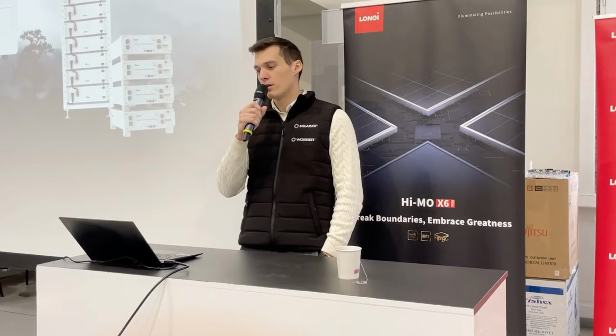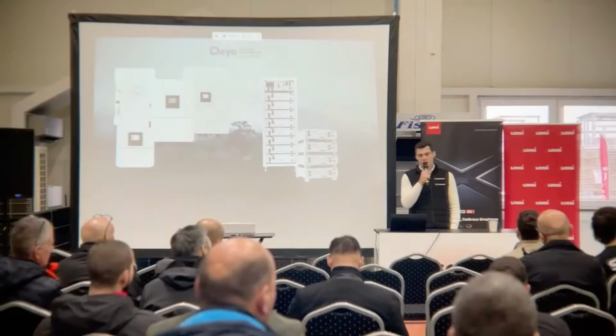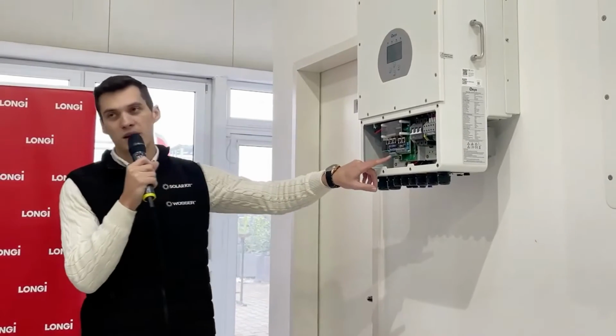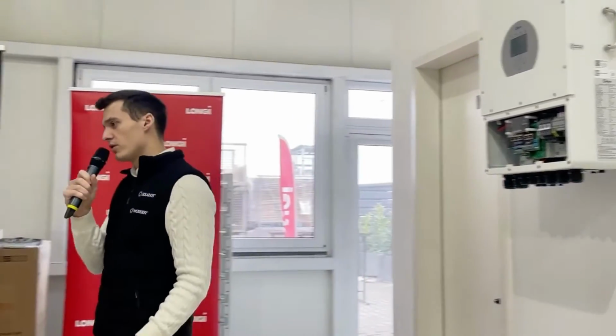You also get a thermometer with the inverter when you purchase it, so it's included in the packaging, and you can add it to the battery. The inverter will be able to monitor the temperature of the battery, even though they are not connected through communication, using the thermometer on pin 1 and 2 on the lower side. It's really important because here you also connect the CTs. There are 8 pins, and with 3 CTs you would only use 6 pins, because the first 2 are for the thermometer.